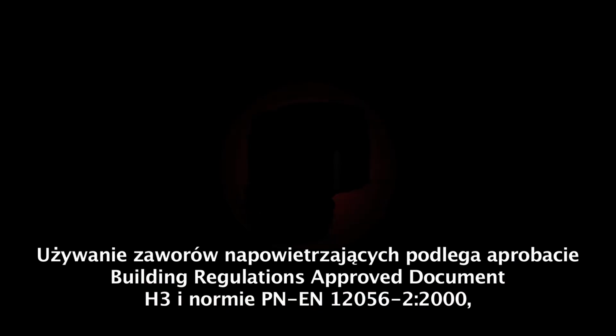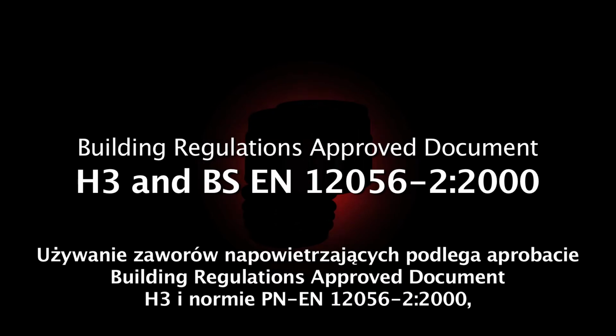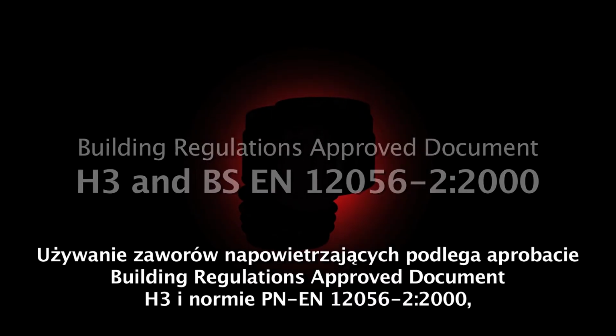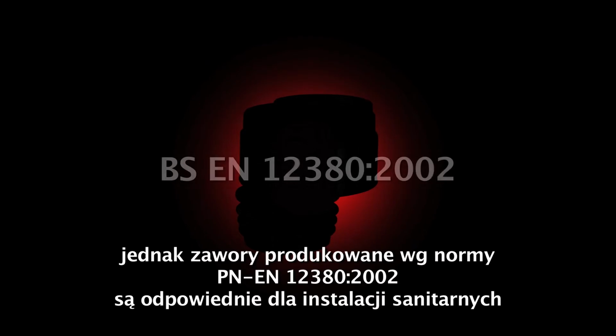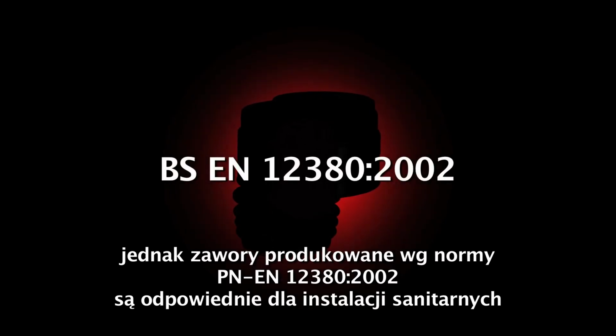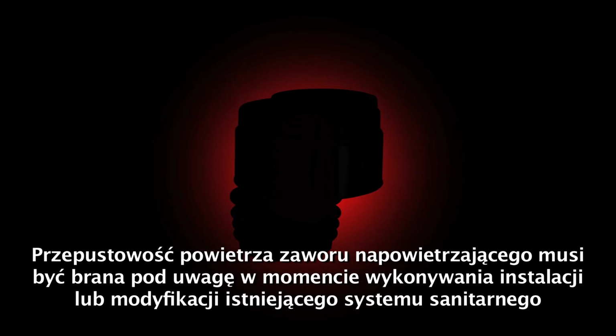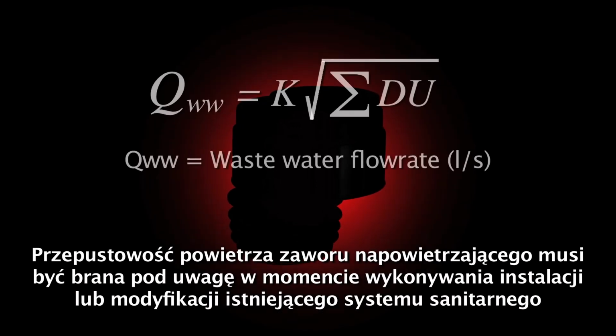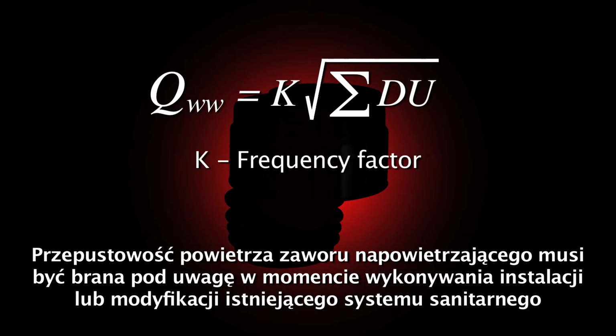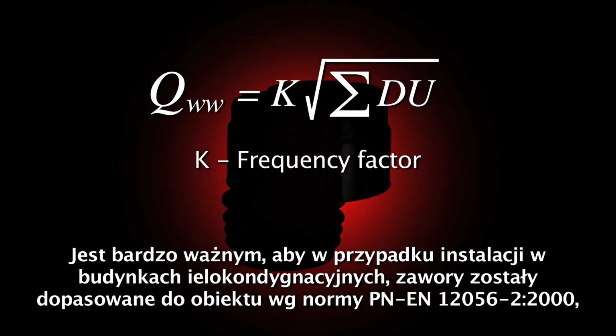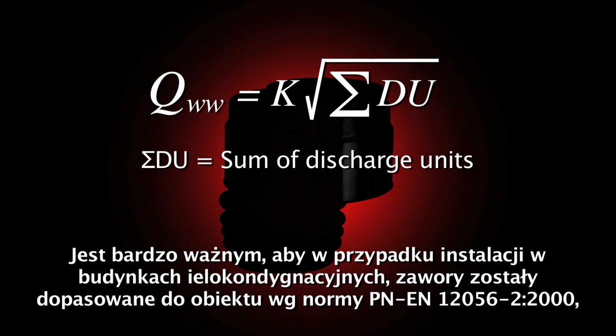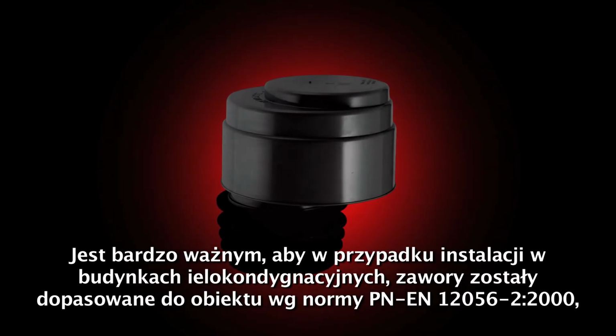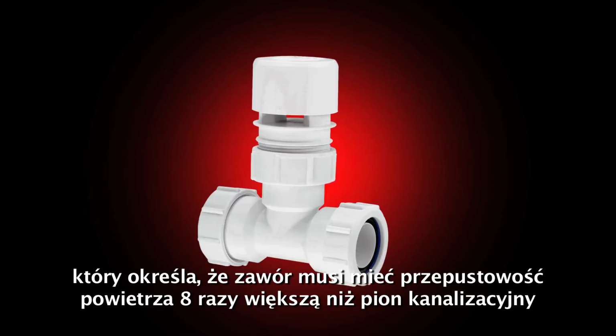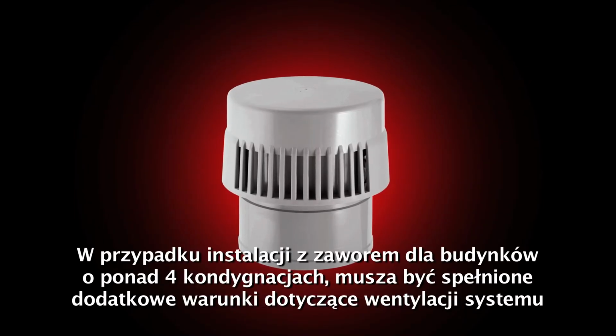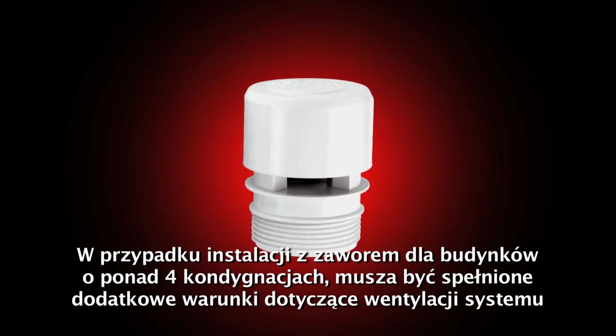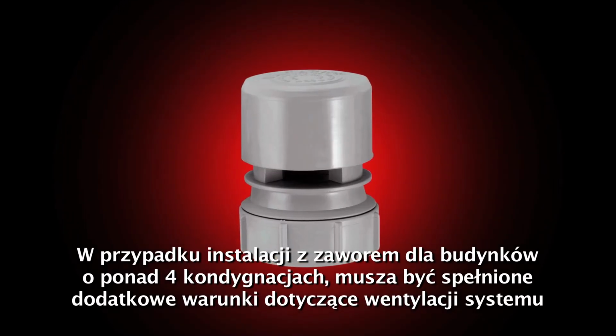The use of AAVs is approved under Building Regulations Approved Document H3 in BS EN 12056, though only AAVs manufactured to BS EN 12380 are suitable for use in sanitary pipework systems. The airflow rate of any AAV needs to be taken into consideration when the system is designed or being modified. It is important when dealing with multi-storey buildings that the AAVs are sized correctly and in accordance with BS EN 12056, which states that the valve has to be 8 times the peak airflow rate of the soil stack. Where an AAV-equipped drain serves more than 4 stories, there are specific rules about how the drain should be vented.